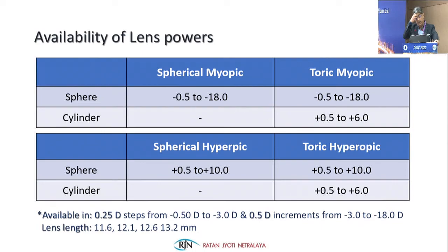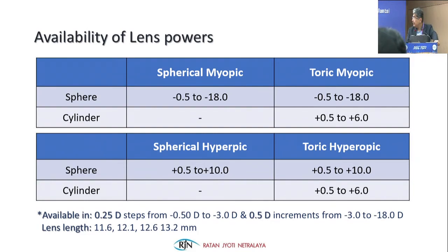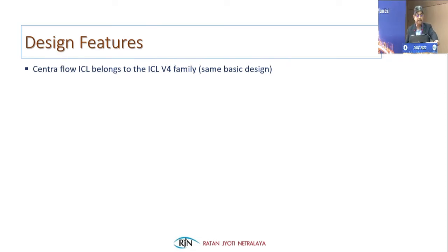ICLs are available in spherical power from -0.5 to -18 diopters, with toric correction of +0.5 to +6 diopters, and in hyperopic range from +0.5 to +10 diopters. They come in steps of 0.25 diopters from -0.5 to -3 diopters and in steps of 0.5 diopters from -3 to -18 diopters. Lens sizes available are 11.6 (rarely used), 12.1, 12.6, and 13.2 — the maximally used sizes.